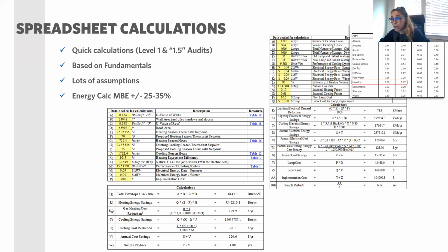Or for example, if we have trend data, we can figure out the heating season hours and cooling season hours. But if that's not available, there are some tables we can use, and these spreadsheets are built for Texas specifically. So we can look at Houston or Austin to find the most appropriate hours. And especially in our interpretation of the levels, for level 1 we said our accuracy needs to be within 30%, and these calculations are giving us that accuracy.